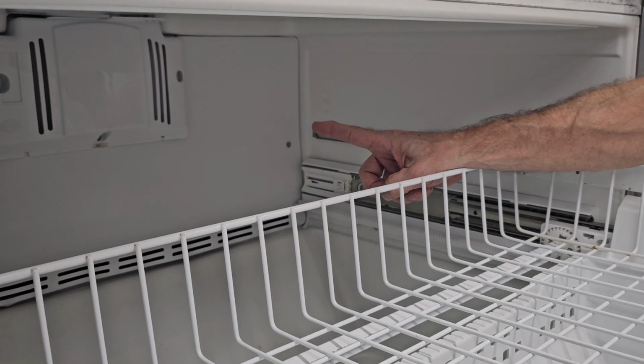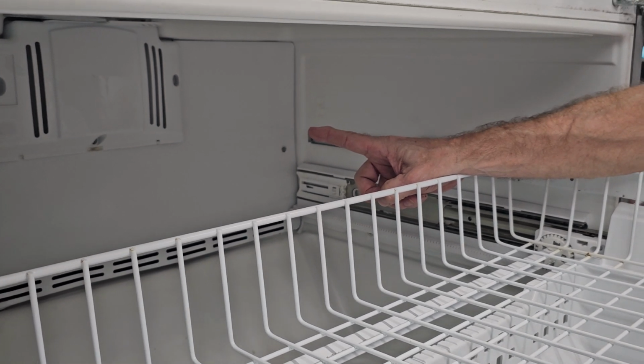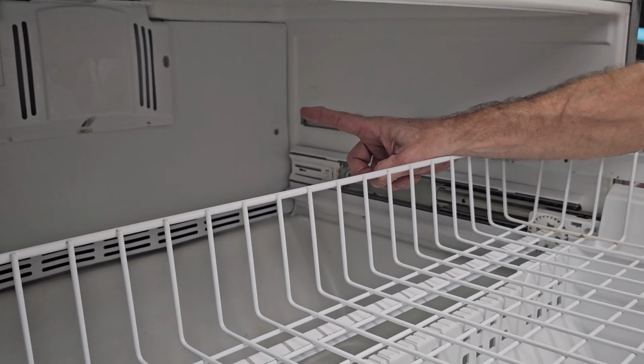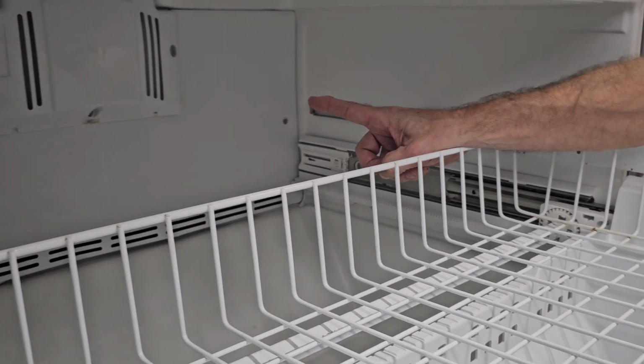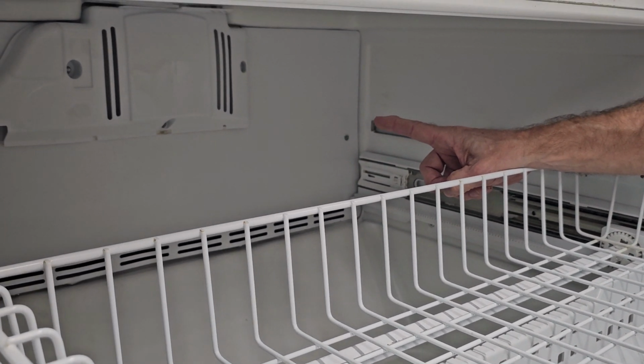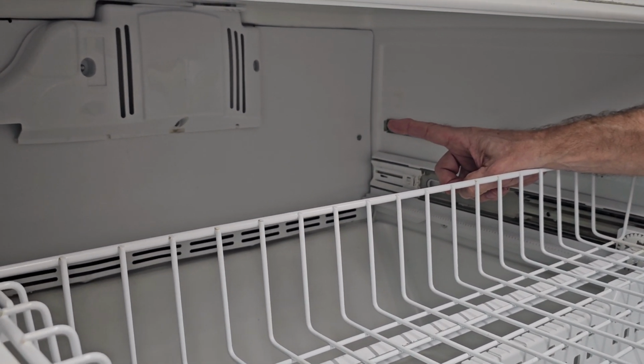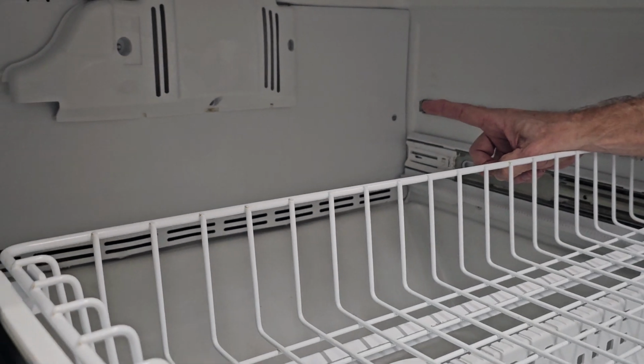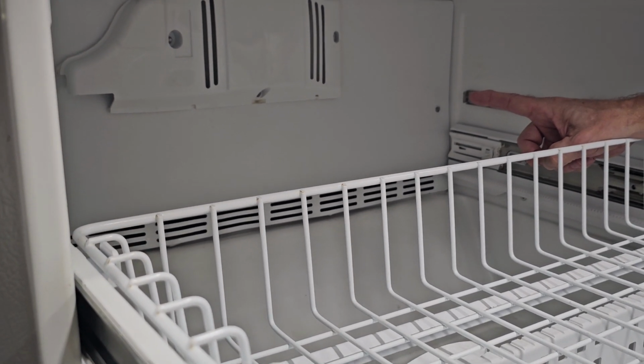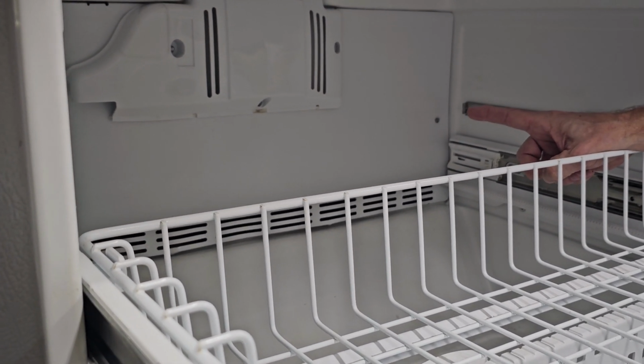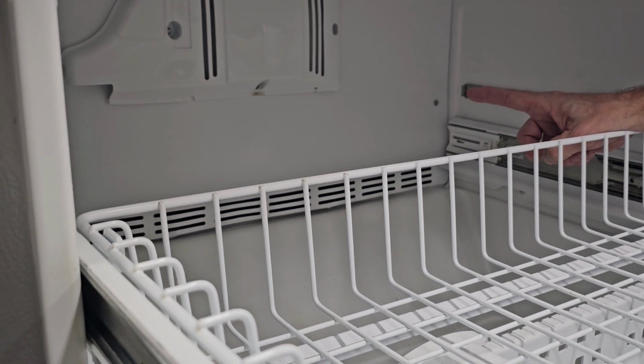Why do we have an evaporator sensor? It senses frost buildup, usually for defrost, not necessarily to tell it to defrost, but when it goes into defrost, it controls the defrost heater. That's what tells the control board to stop defrosting because it's so hot back there.